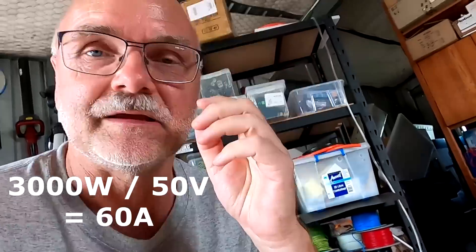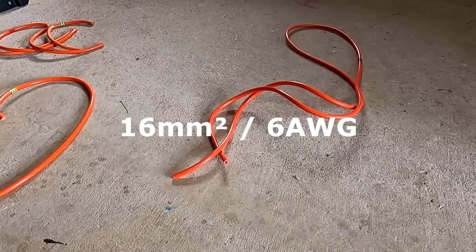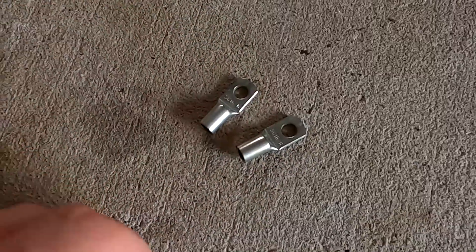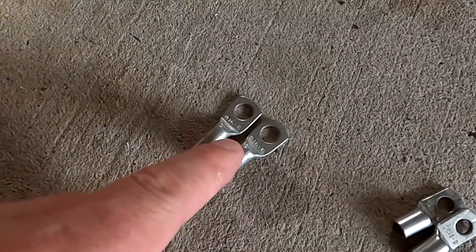Because this is just a three kilowatt inverter - 3000 divided by 50 is around 60 amps - I'm perfectly happy to utilize our offcuts of the 16mm cable. I've got some ring lugs already: these are 6mm for the inverter and 8mm for the Victron.